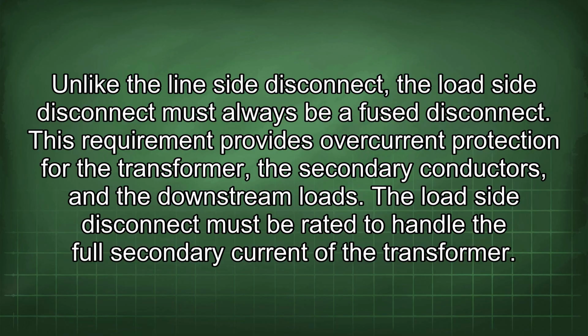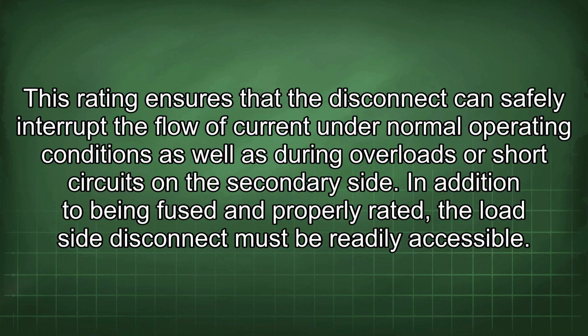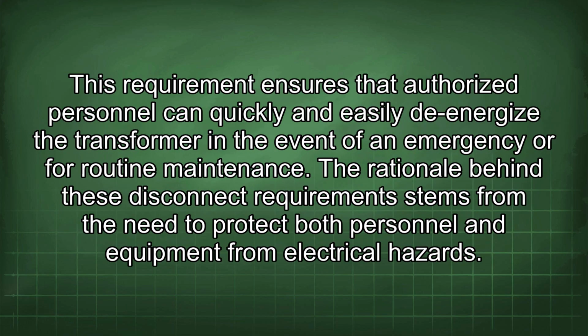The load side disconnect must be rated to handle the full secondary current of the transformer. This rating ensures that the disconnect can safely interrupt the flow of current under normal operating conditions as well as during overloads or short circuits on the secondary side. In addition to being fused and properly rated, the load side disconnect must be readily accessible.